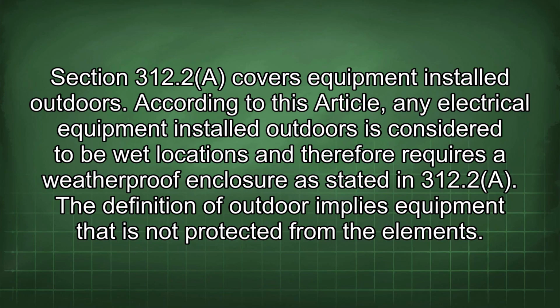Section 312.2 covers equipment installed outdoors. According to this article, any electrical equipment installed outdoors is considered to be wet locations and therefore requires a weatherproof enclosure as stated in 312.2a. The definition of outdoor implies equipment that is not protected from the elements.